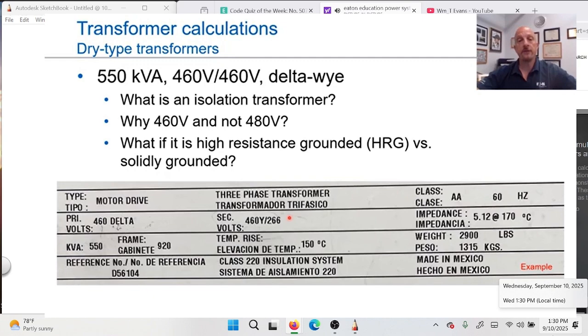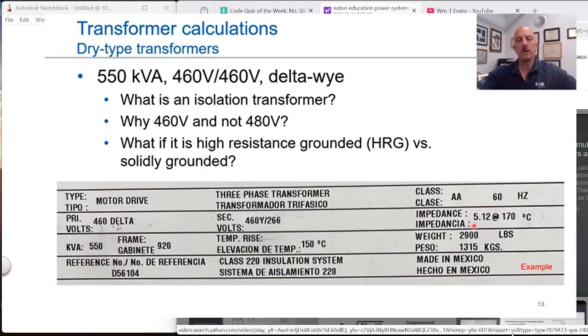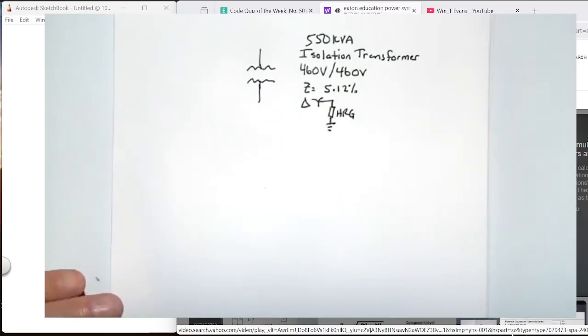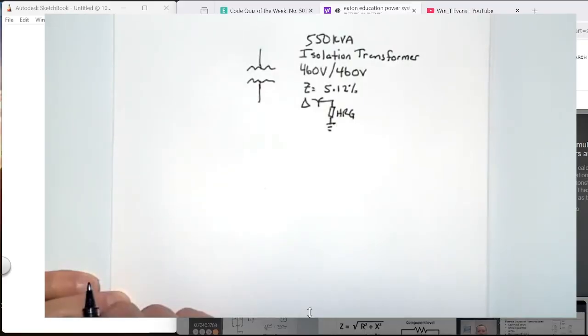Now this transformer is a little bit unique. This is called an isolation transformer. And again, isolation transformers might be used in front of a motor drive as is shown here. The interesting thing about isolation is, again, it goes 480 in, or 460 in this case, and 460 out. For the next transformer, we have this unique isolation transformer. And again, it's 550 kVA, 460 volt rated in, 460 volt rated out.